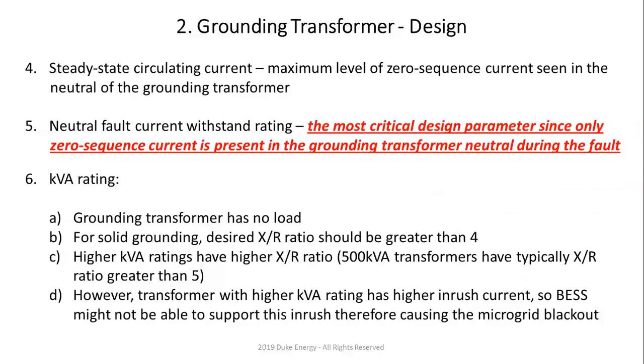You have a design that's empirical plus simulations. Then you have to simulate line-to-ground faults. And also you have to test something somewhere in the yard or in the system where you have it. And to be honest with you, I have seen differences between design versus simulations versus actual, right? So everything has to be designed with what you see literally in the field. And sometimes we need to fine-tune some of our approach or some of the design parameters in order to get to this. And the last but not least is the KVA rating, right?